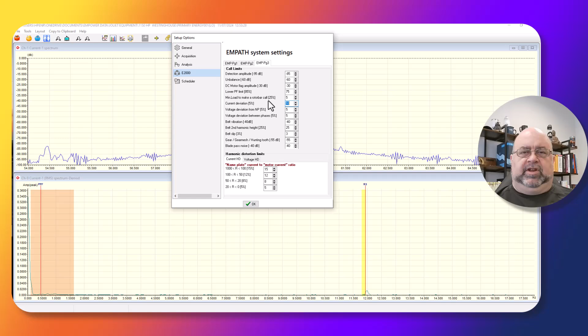And these are general by overall machines. You can tighten things up, loosen things up, especially if you're doing continuous monitoring. I always set the minimum load to 5%. Not clear why, there was a big push by one distributor to keep it at 25%. So for whatever reason the programmer keeps it there, but we normally test motors that are unloaded when we're at repair shops, sitting on the thing, regardless - you've heard me talk about it before, regardless of...